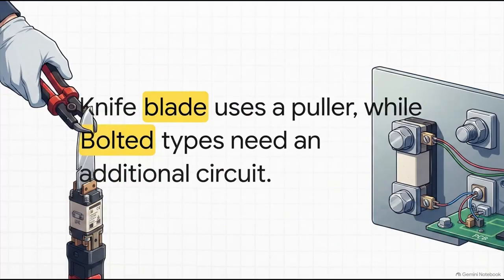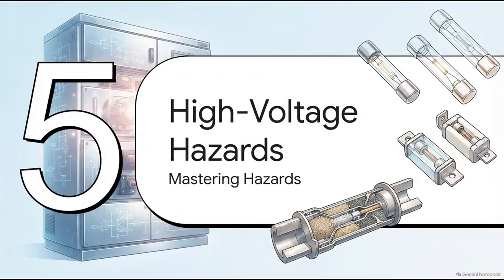Now, while they are maintenance-free, there's a bit of a catch. Once they operate, the whole fuse element has to be totally replaced. Plus, they do throw off some heat during faults that can mess with nearby switches if you're not careful. There are 2 main types you'll run into here. Knife blade type switches, which actually require a very specialized fuse puller just to safely swap out the wire on a live circuit. And then there are bolted types, where the conducting plates are physically bolted down to the base. For those, you literally need a whole additional circuit just to take the switch out without getting a nasty electrical shock. Okay, we've scaled all the way up from your living room out to massive industrial switches.